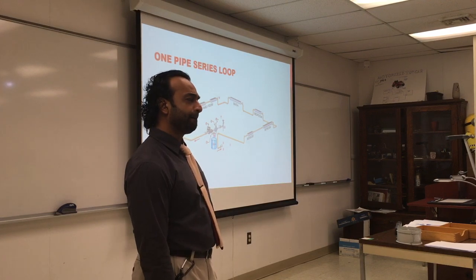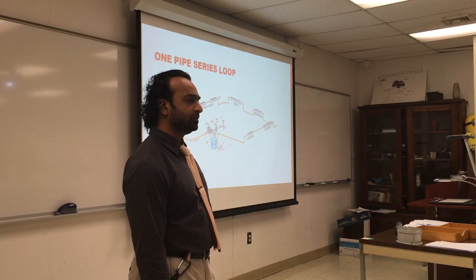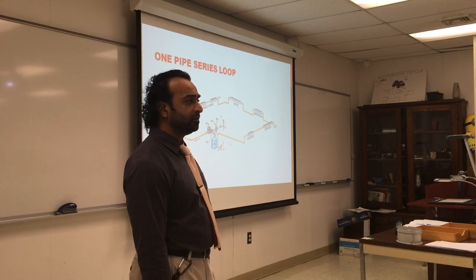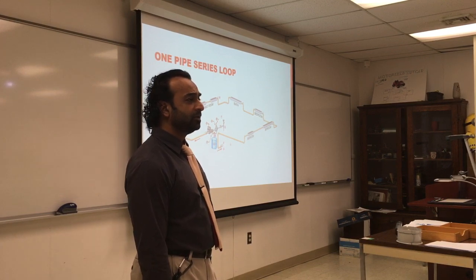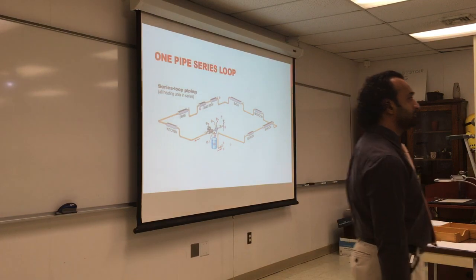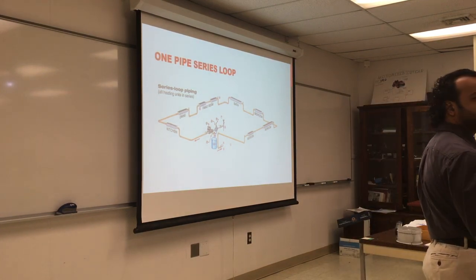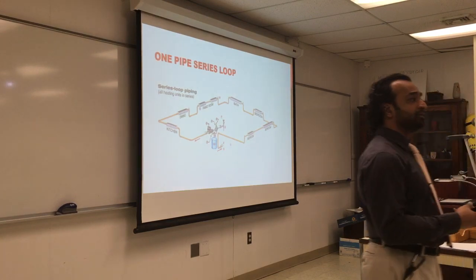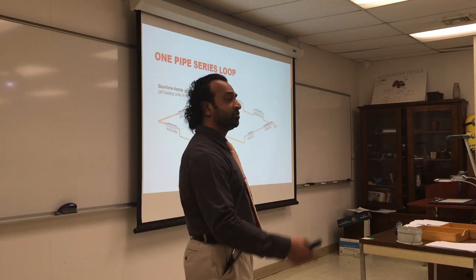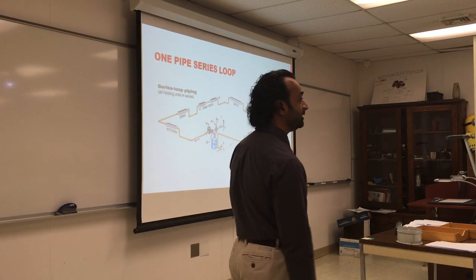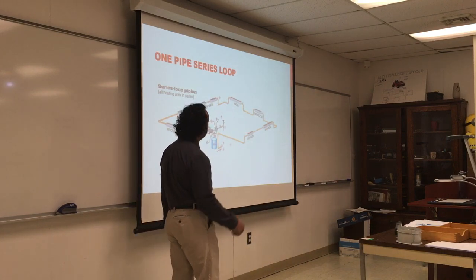Student question: if the heating drop wasn't too bad for two or three radiators, could you do a return after three and come back? Instructor: you could, if you do the proper pressure drop calculation. We're mostly concerned about the pressure drop, not just the temperature. If the pressure drops and velocity becomes very low, the first radiator will pull all the heat out and the radiators after that will have no heat left — resulting in high heating in one area and low heat in another.